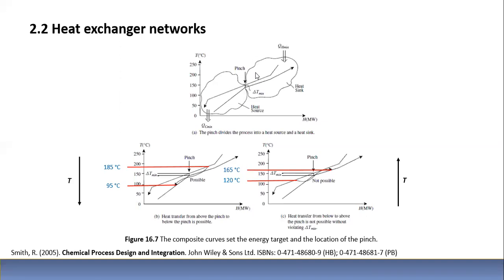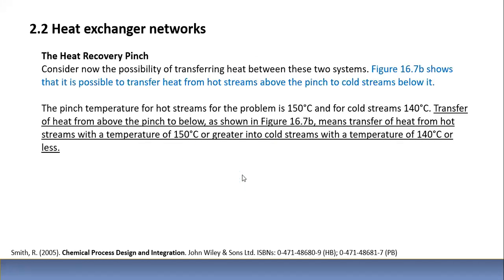Also, we could see how the process acts as a heat sink above the pinch, where we are requiring a minimum amount of energy, and how this is the pinch, and how the process is acting as a heat source below the pinch, where heat is rejected. And there is a minimum amount that needs to be absorbed by a cooling tower provided. Consider now the possibility of transferring heat between the two systems. Figure 16.7b shows that it is possible.